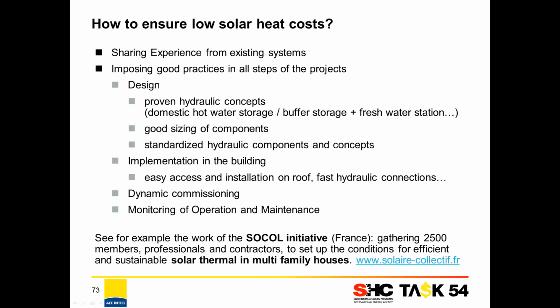The dynamic commissioning is also very interesting. It consists in checking that the solar system is actually delivering the expected yield in the first months of the real operation of the system, and it can help correct the regulation system, control system, or other issues quickly. During the lifetime, it's also important to monitor the operation.